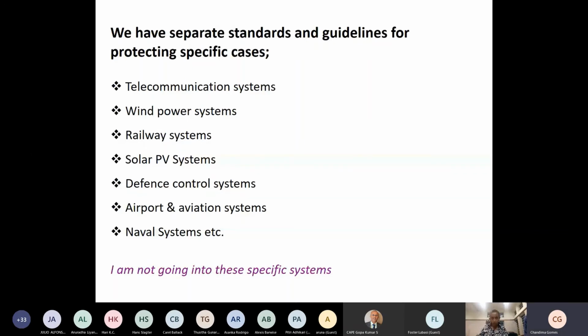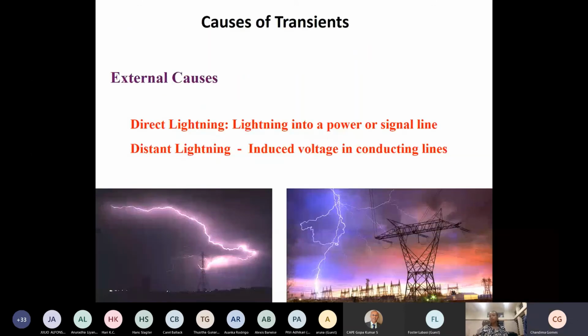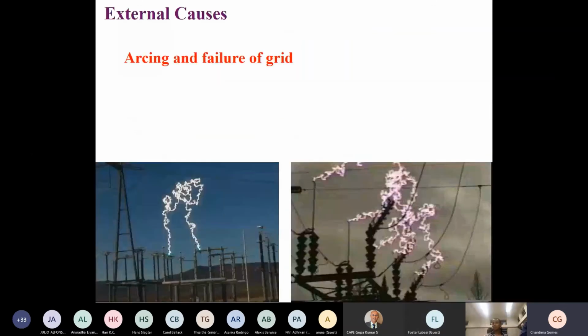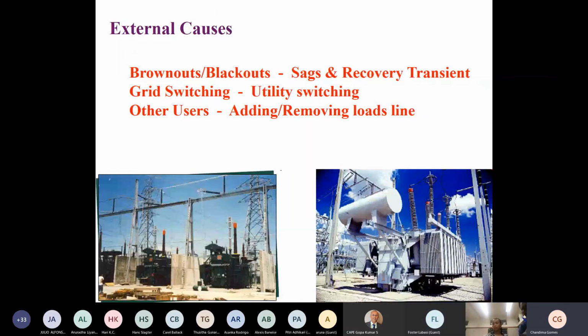Okay, if I go very quickly over the causes of transients, lightning is a very basic cause of transient currents into your system. It may be direct strikes or even distant lightning. But there are some other cases as well, like arcing of grids, grid failures, and so on. Then brownouts, blackouts, grid switching, other operations like adding or removing loads. In all these cases, you may get transients. So it is not only a phenomenon related to lightning. Lightning is a very predominant cause of transients, but there are many others as well.